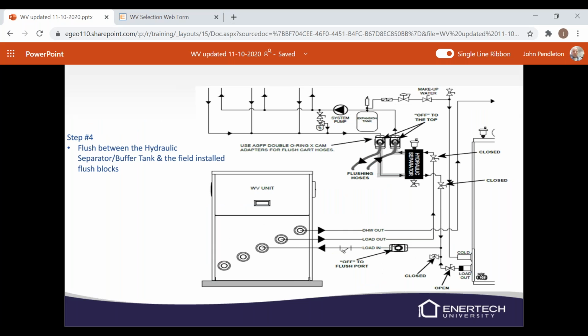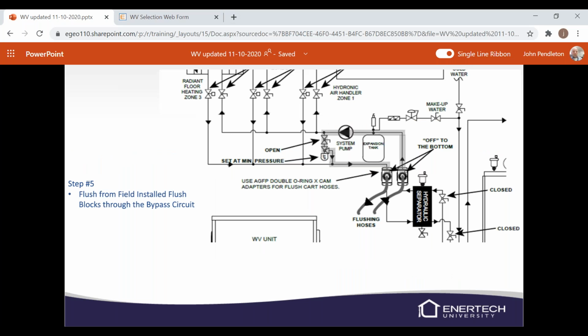After that, we can go up on the other side of your hydraulic separator or buffer tank to your external field installed flush blocks, and we can flush between there. When you do the external pumping, you've got that little triangle there, that's your external pump. You're probably going to want to put a bypass valve in the load in and load out lines, so that if you don't have proper water flow, or this pump is pushing more flow than is required for that zone, the extra flow will be bypassed and return right back to the hydraulic separator or your buffer tank. So we want to flush out that bypass. Close off all your zones, and we'll just flush through your bypass.